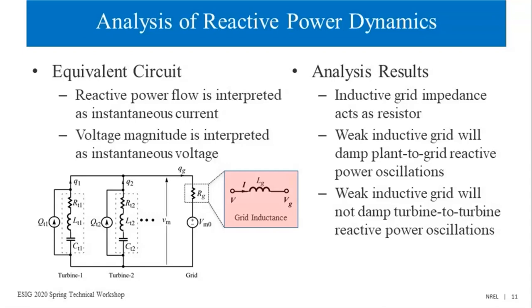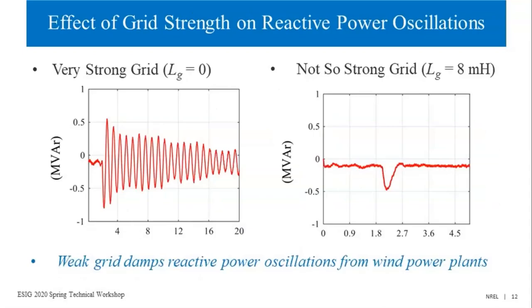So if you represent the reactive power dynamics in this equivalent circuit manner, the grid impedance will act as a resistor. Having a weaker inductive grid will basically damp these oscillations from a wind power plant, which is very interesting. We usually see that the weak grid is mainly responsible for stability issues, but here we are seeing that a weak grid can actually provide damping. And this was also verified experimentally.